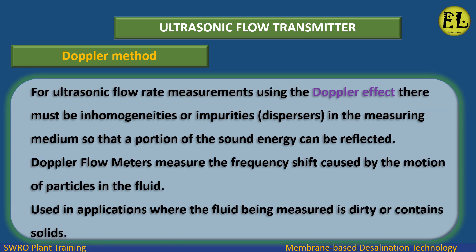Doppler method: For ultrasonic flow rate measurements using the Doppler effect, there must be inhomogeneities or impurities — dispersers — in the measuring medium so that a portion of the sound energy can be reflected. Doppler flow meters measure the frequency shift caused by the motion of particles in the fluid, and are used in applications where the fluid being measured is dirty or contains solids.